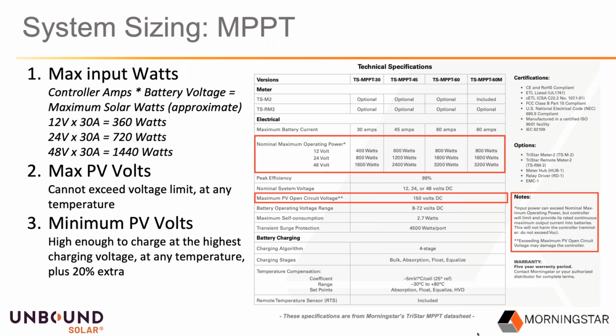One note about this, it kind of helps demonstrate why you would move up to a higher voltage for a bigger system requirement. Sometimes customers will ask us, when should I move up to a 24 volt system instead of 12 volt, or when should I use 48 instead of 24? When is it beneficial? And I think this does a pretty good job of showing why it's so beneficial to move up to 24 or 48 volts for higher power requirement.